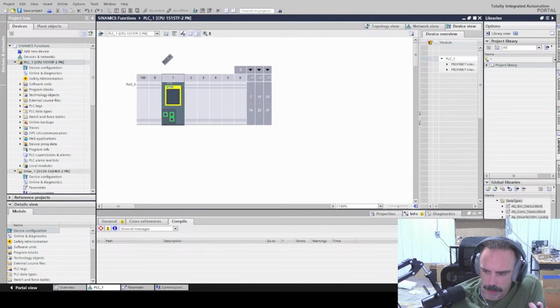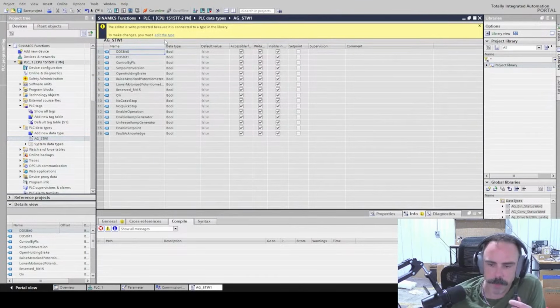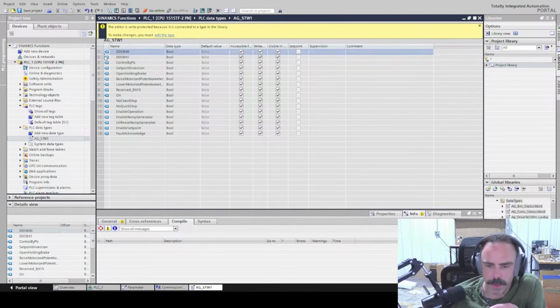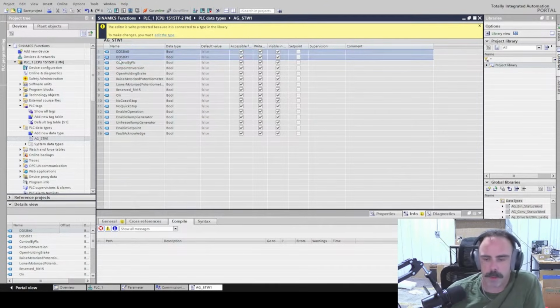But in that, there are these status words. And so I wanted to show you this. So this is the actual control word. And so I updated these 2 free bits. So in the standard 352 Telegram, these 2 values, it's bit 8 and 9 in the control word, but because of the byte swapping, it comes in as this. So I just added these 2 bits.